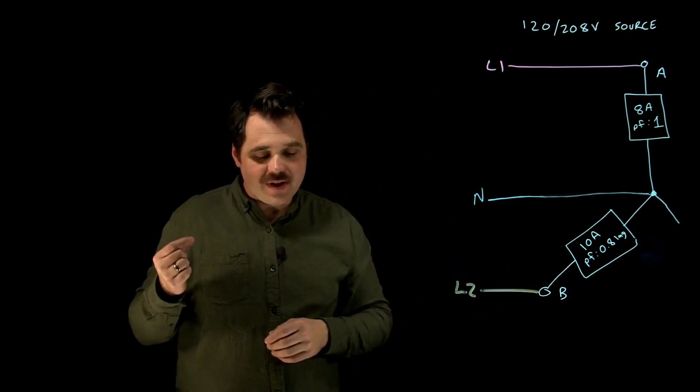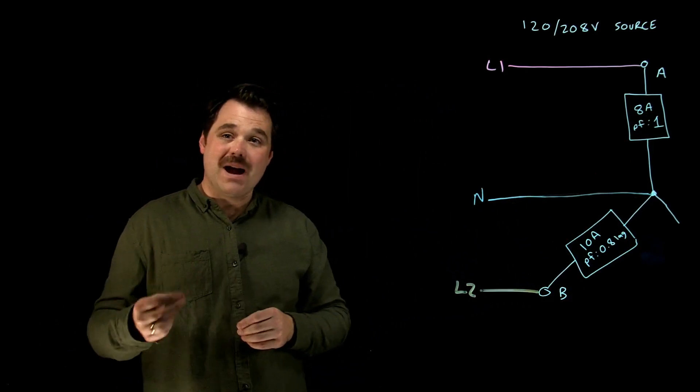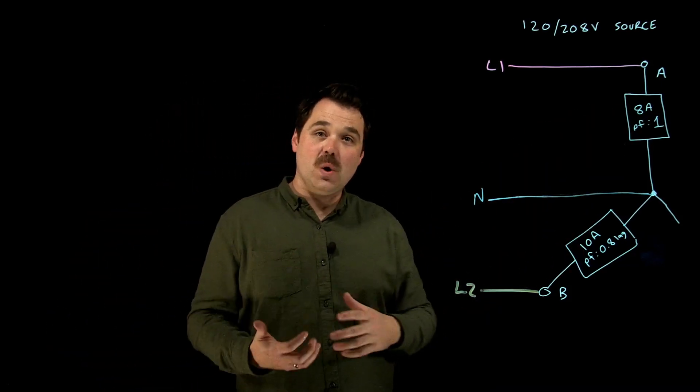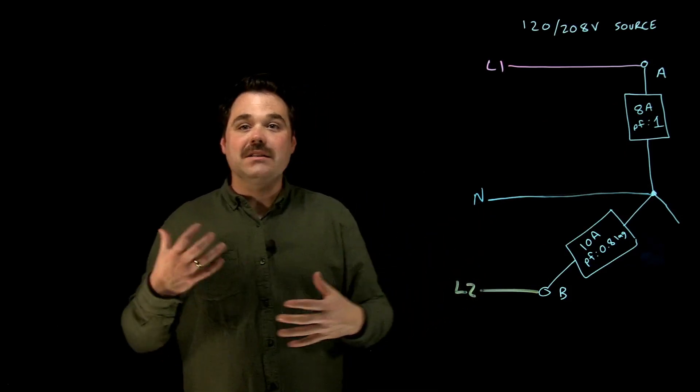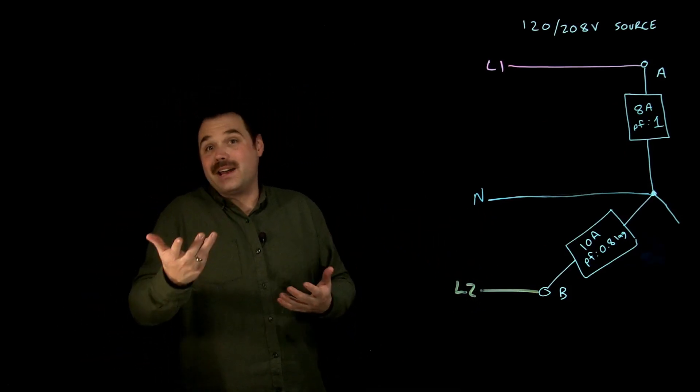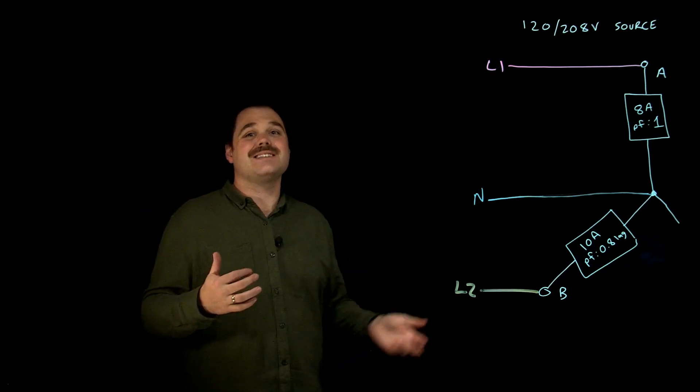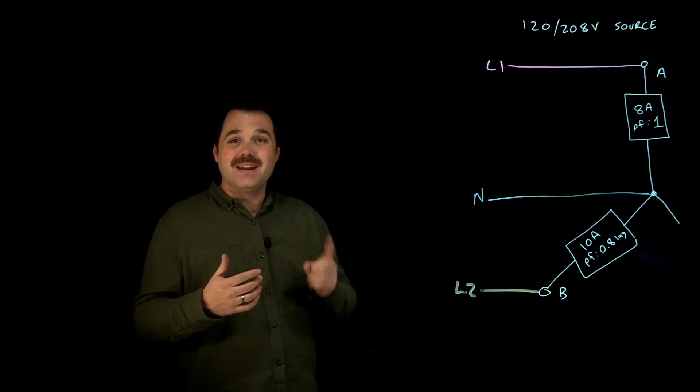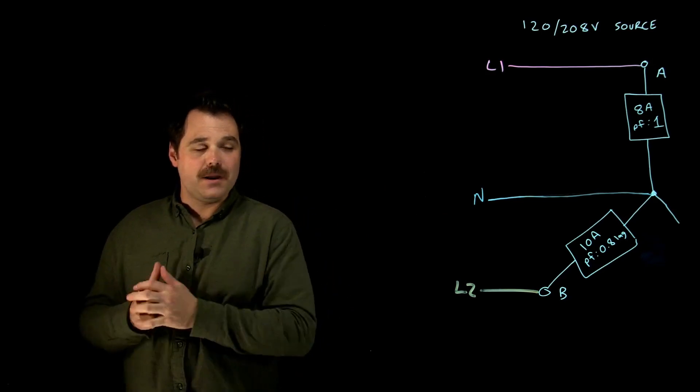It is also there to carry the unbalanced load, meaning if the two phases have a different load on them, the unbalanced load will go back on the neutral. Now that's a similar concept to an Edison three-wire, which we discuss in another video. So those are the two purposes: maintain phase voltages, carry unbalanced load.